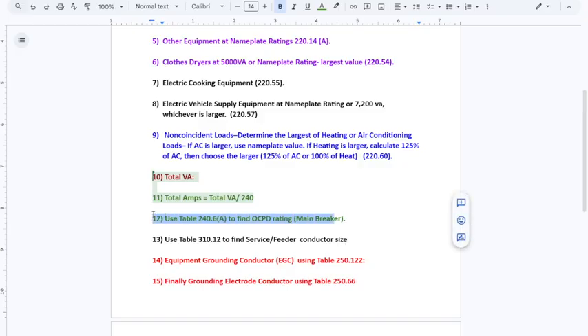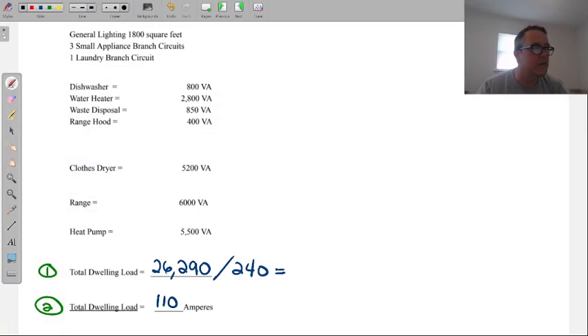All right, so now we have two things to do. We need to find the breaker for this panel - you can go to Home Depot and purchase one - and then we need to find the wire. You'll notice this sends us not to 310.16, which is 99.999% of the time the article we'll use to select wires, except in the one case of dwelling units, where we go to a different article to find the wire.